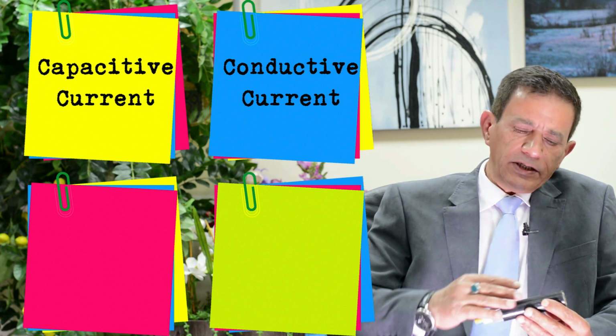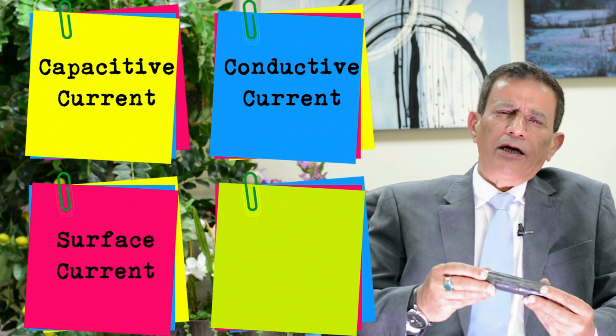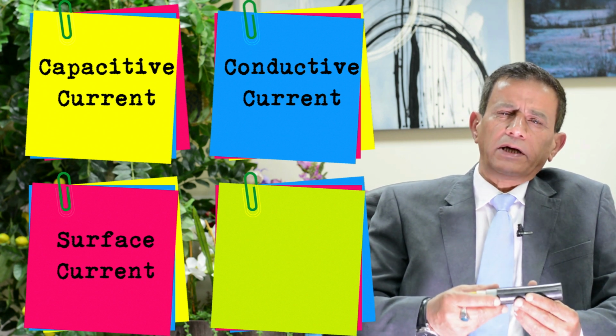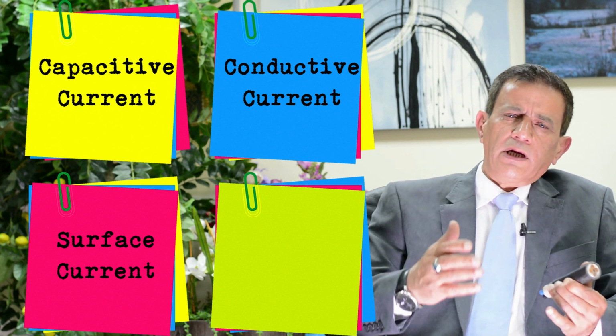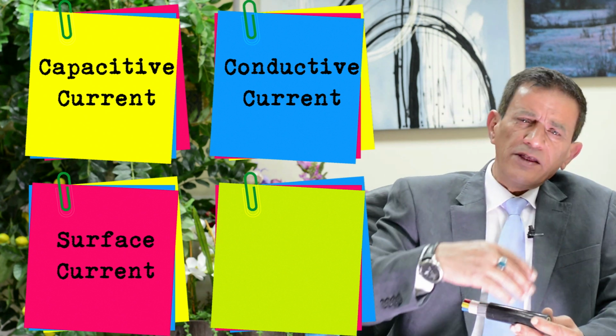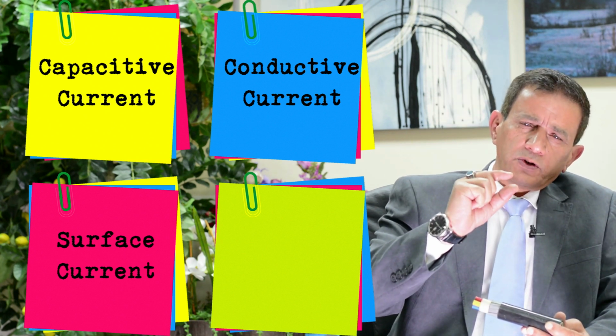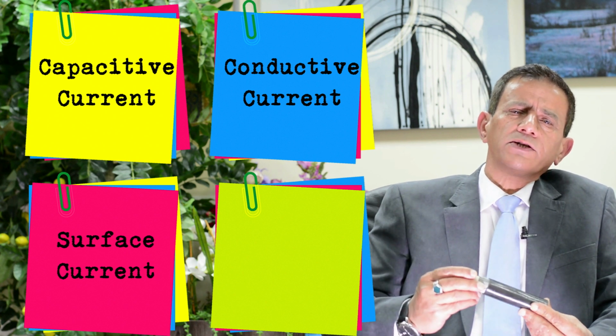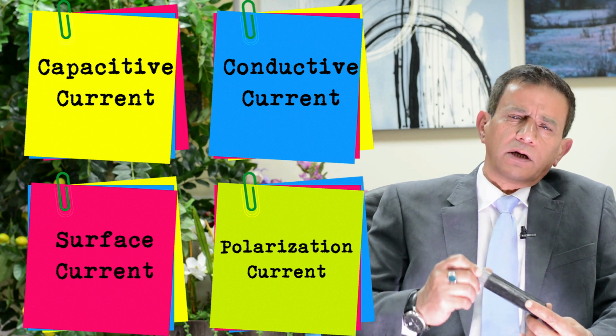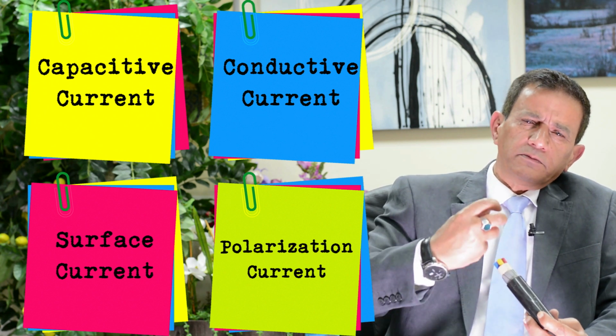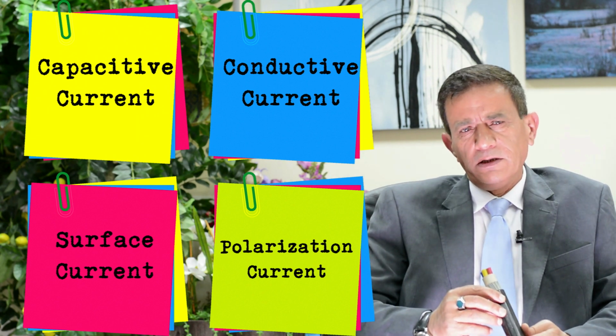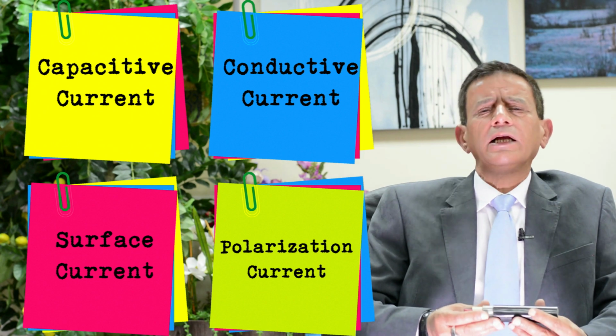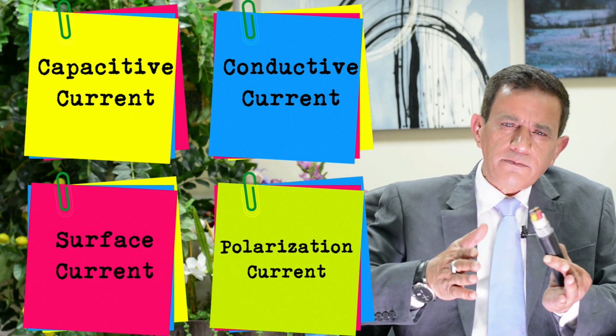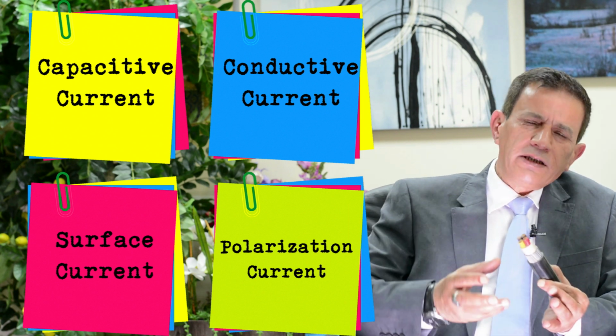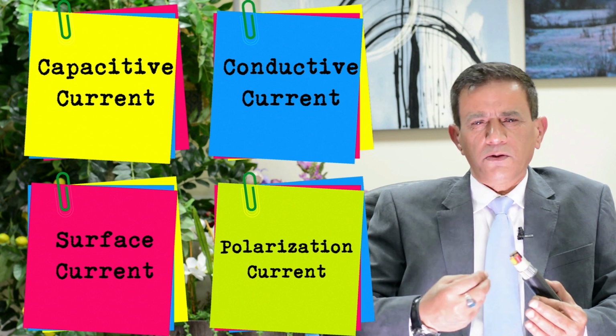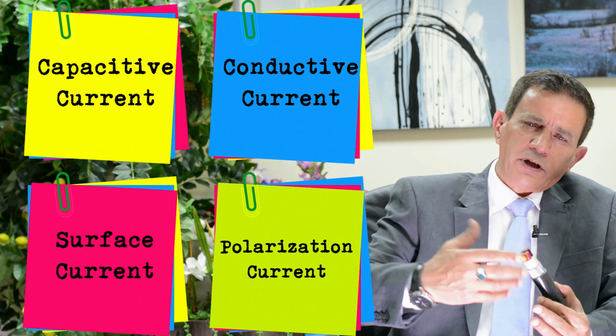Third component is the surface current component. Normally, the insulation material, whether plastic, PVC, XLPE, or porcelain or glass, will have a kind of dust on the outer surface, and this will absorb part of the current for also a short period of time. Fourth component is the polarization component. Any insulation material is hygroscopic in nature, meaning there is some dust or moisture inside this material. So when there is an electric field applied to this material, the particles of the moisture and foreign materials will align themselves with the electric field. This alignment needs some electric current. This also will be for a short time, and it might take up to 10 minutes.